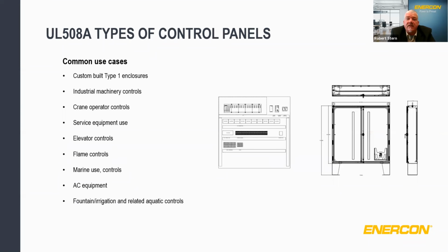So what are the types of typical control panels? Well, a custom-built type 1 enclosure. A panel builder can make just an enclosure, just a bare enclosure itself. Industrial machinery controls, crane operator pendants, service equipment. Elevator controls are a great example of an industrial control panel. Flame controls, for use in marine environments, such as on a barge or a pumping unit on naval equipment.